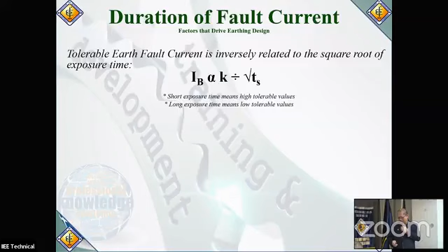Ano yung mga normal na tinitignan or basis to set your trip point or the trip current or the trip time, or what we now call the time to clear the fault? What is the time to clear of the fault? So yun yan. Medyo crucial yan. If you do calculations for IEEE 80, malalaman mo dyan na yung time to clear is one of the most important factors. Napakalaking impact niya. Okay, the allowed current value must be based on the clearing time of the primary protective devices.